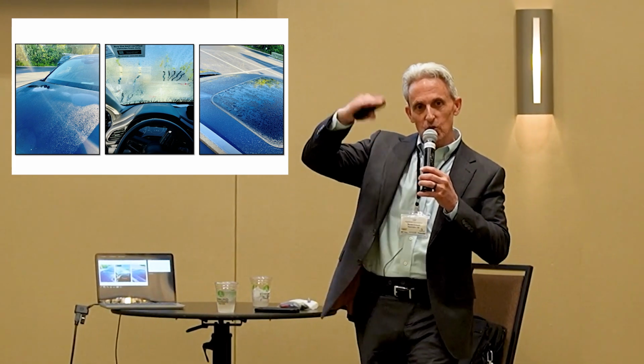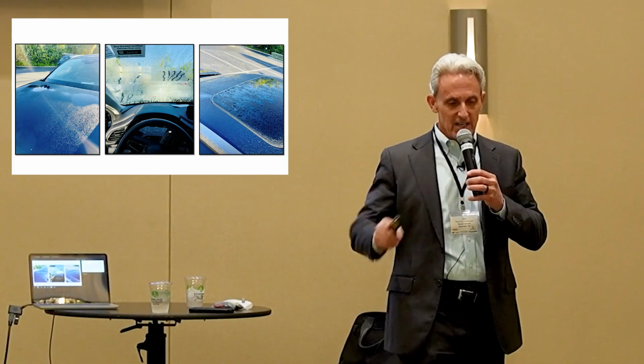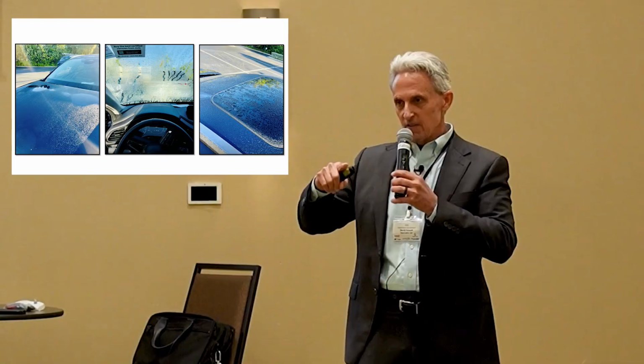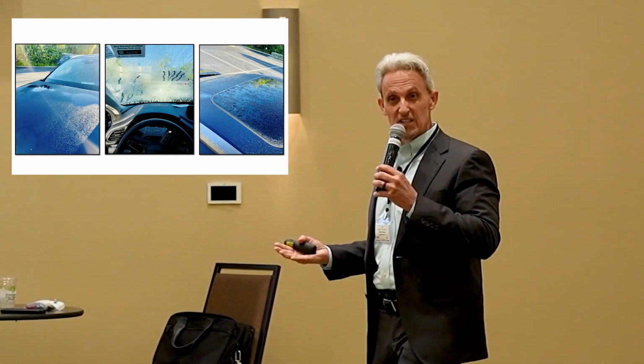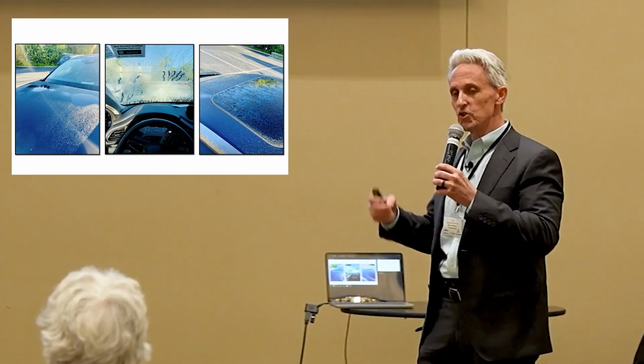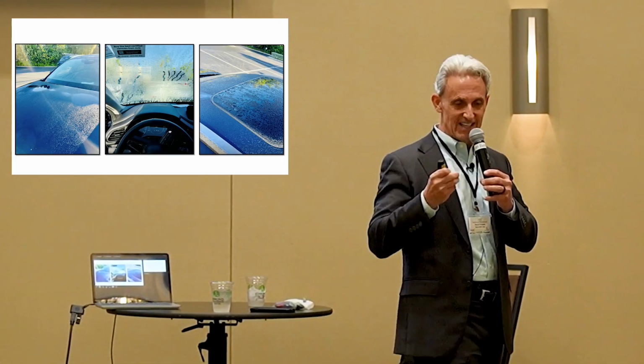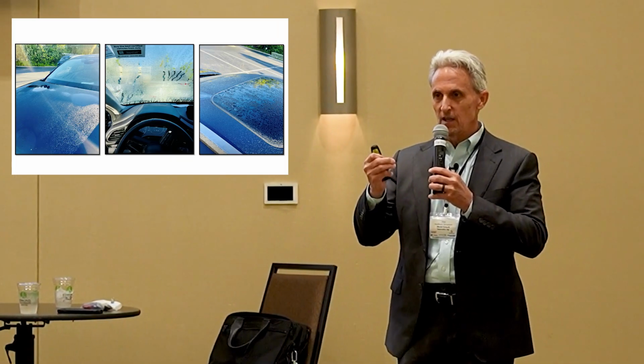There's no radiant cooling effect there. It's just those surfaces exposed above. So anytime you chill a surface below the dew point temperature of the air that surrounds it, that surface will condense moisture, and you will, in theory, dehumidify the air, right? That's how we do it. Does that make sense?